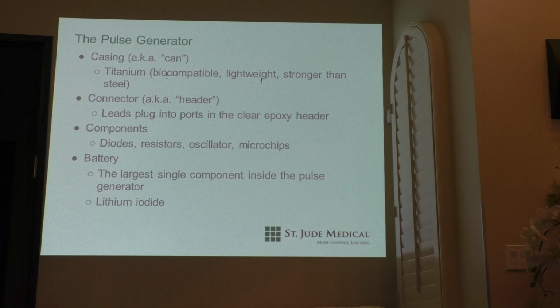So normal pacing outputs are in the volt range, from about 1 volt to, I think, the maximum on most devices of 7.5 volts. The batteries only go to 3. So how do you get 7.5? You have to store it, and you use a capacitor to do that. So you charge the capacitor twice, basically, or you link it up in series, in order to get the voltage multiplier. And that's for someone that just will need like a 6-volt charge every day, every beat. Some people require higher outputs.